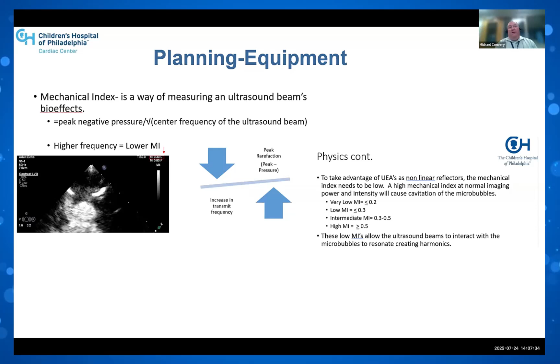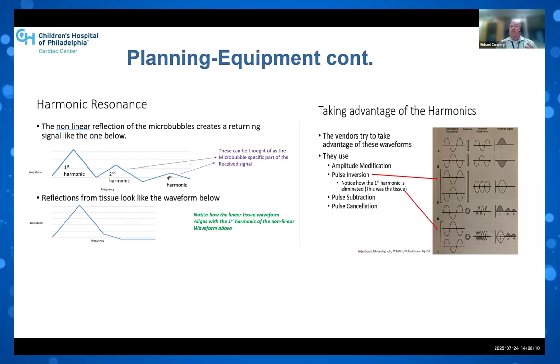So since they're nonlinear reflectors, they make that nice harmonic resonance, the microbubbles, and just focus on that first harmonic there on the left. If you compare that to the tracing that I made there on the bottom, that's what the harmonic reflection looks like coming back. The machines will electronically use things like pulse inversion and amplitude modification to remove that first harmonic, and that's what gives us that really nice black and white look. So the tissue effectively goes away and we're focusing on the microbubbles.